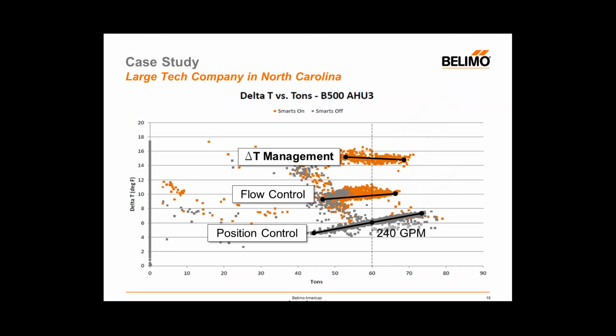In flow control mode, remember, it's the same valve on the same piece of air equipment. It's the same air handler, same valve, just a different control strategy at the valve. We didn't change the automation system at all either. Now we're at 10 degrees delta T. 60 tons of cooling gets us almost 100 gallons a minute less to create the same amount of cooling.